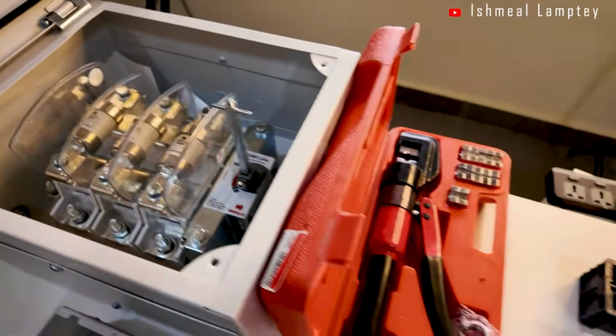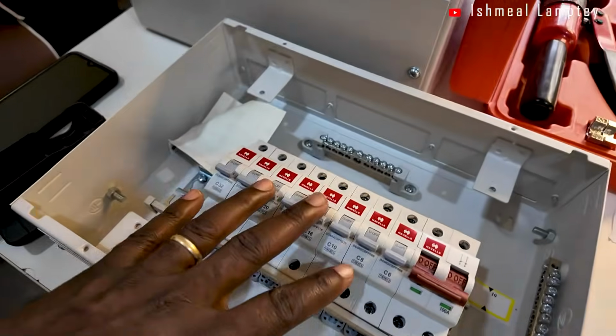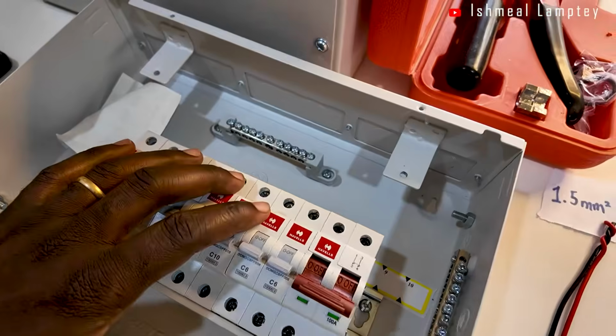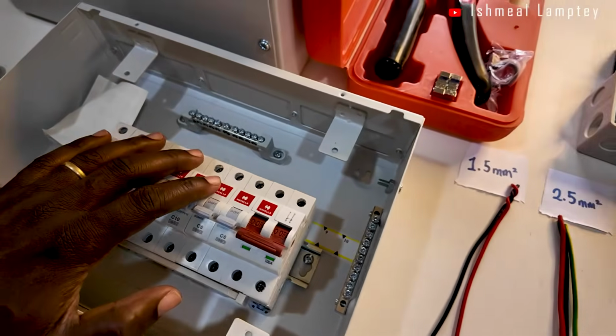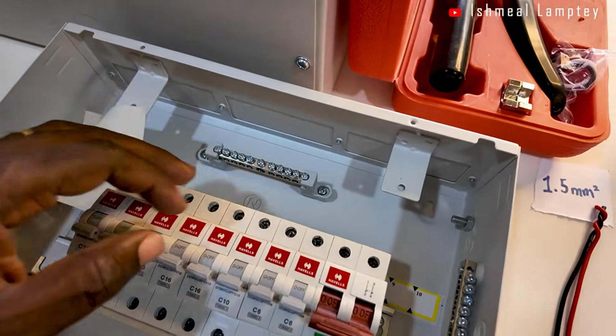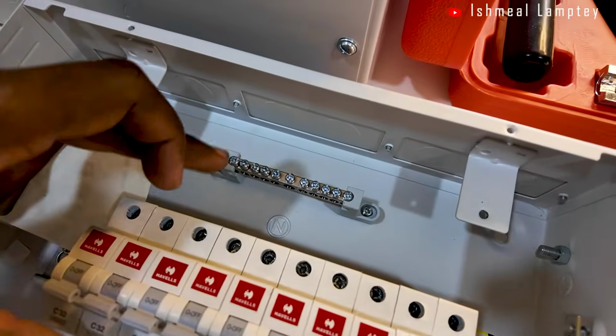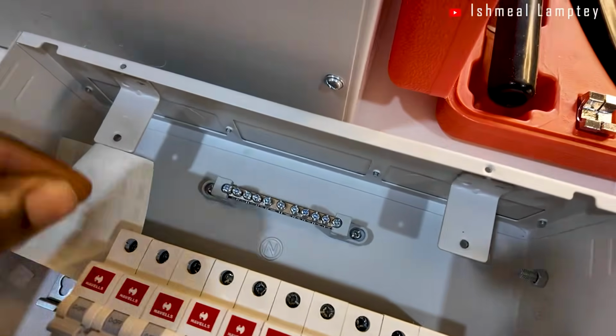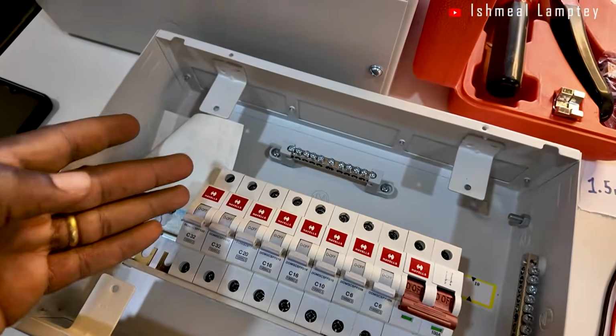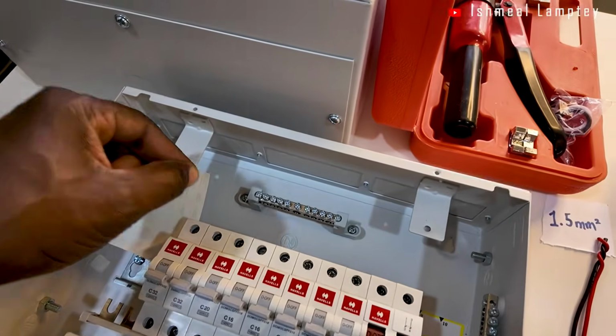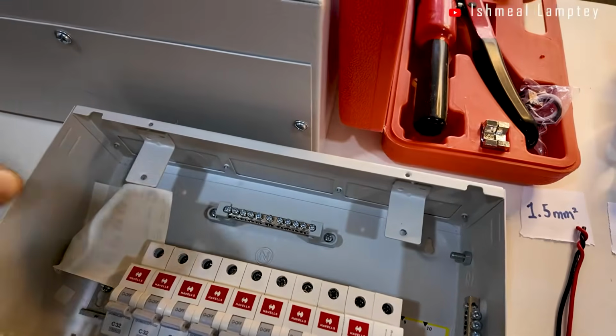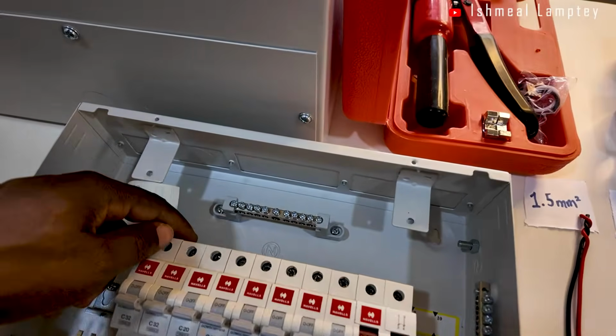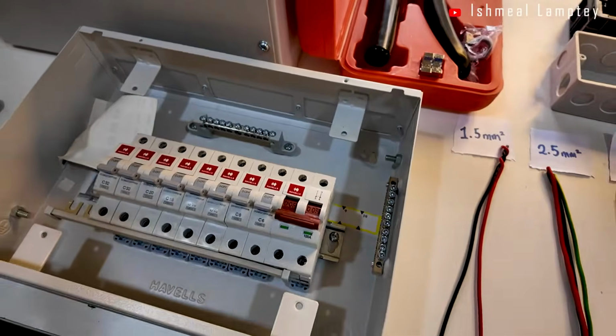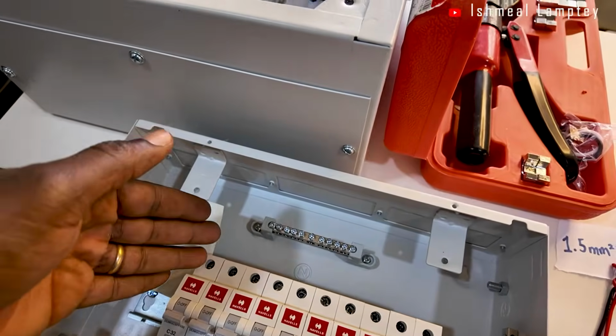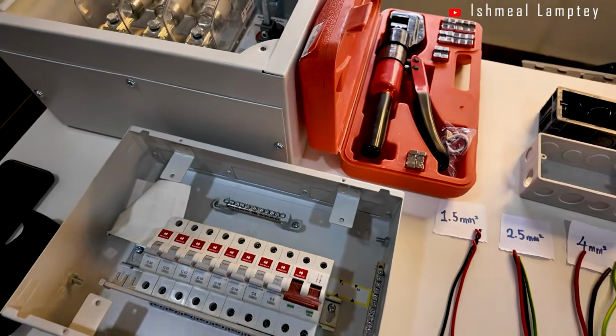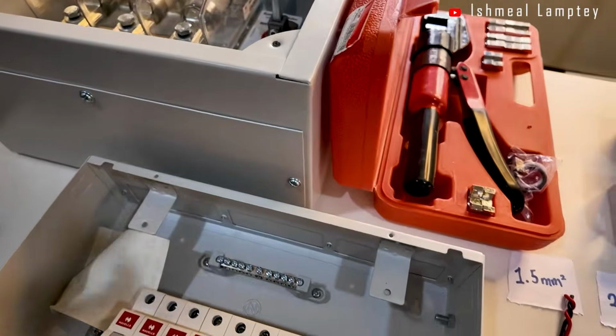And it's the same thing when the terminations are being done in your SPN or maybe your distribution board. In this case, if you don't have the cables properly terminated in either the breaker as well as in the bus bar, whenever there's load, maybe more load, it starts causing sparks. You may not see it because this is closed, of course. And once these sparks happen, it causes the cable to melt, and over time it catches fire and begins to spread, and then it causes your homes to burn down.